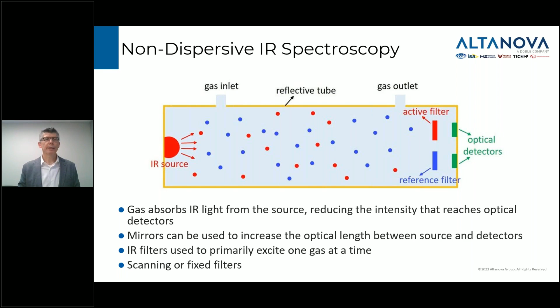And so, as you can imagine, if there's more gas present of a given absorbing species, there will be more attenuation, and there'll be less of that light reaching that detector as it propagates through the gas. And the filters can be either static filters, just fixed optical elements, or there's even a solution out there now that uses a scanning method to make a tunable filter for an NDIR monitor.